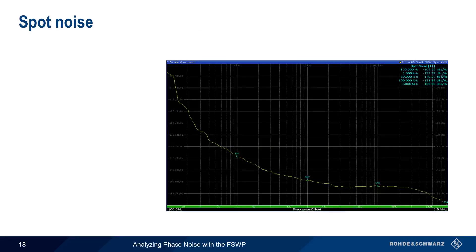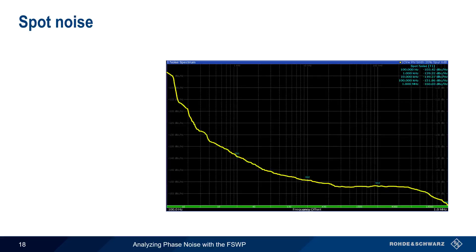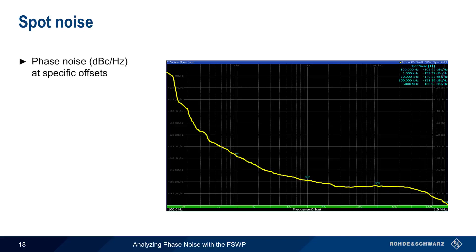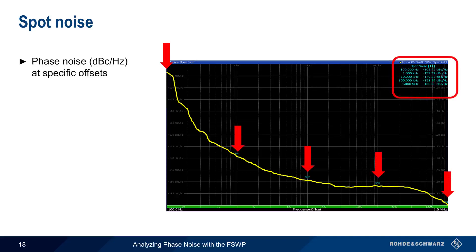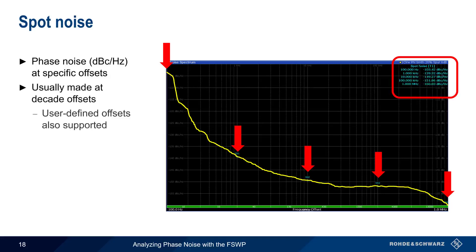Let's start with spot noise, since this is another common way of representing phase noise measurement results. In addition to the standard single sideband phase noise plot, it can be helpful to have numerical values of phase noise at different offsets. These spot values are normally reported in table form at decade offsets, but spot noise at user-defined offsets is also supported on the FSWP.